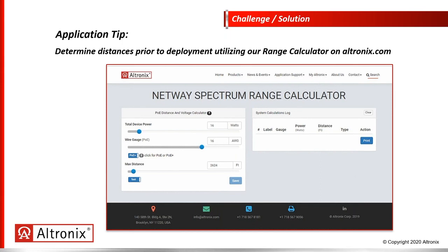Remember, we're pushing power on the copper pair. If we need, as shown in this screenshot, a total of 16 watts of power at the remote end, and we choose 16 gauge copper wire, we can send that power a maximum distance of 2,624 feet. This tool takes into account voltage drop, provides distances in feet or meters, and lets the user print and save the system calculation log for submittals or future reference, useful when different locations require a different gauge copper due to distance or wattage requirements.